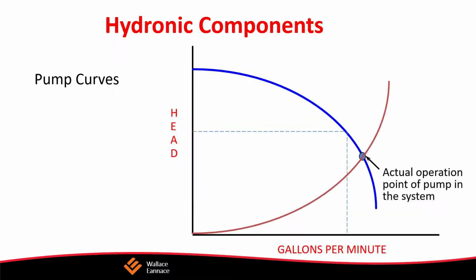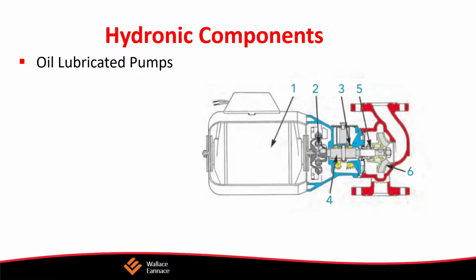First thing we do is we measure the longest run. That is the point from the boiler to the furthest piece of radiation. We measure that distance and we add 50% of this for fittings. We multiply that times 0.04. Remember, we wanted a velocity. If we had 100 feet of length, and we multiplied it by 0.04, that's going to give us 4 feet per 100. And that would be the required pump head.